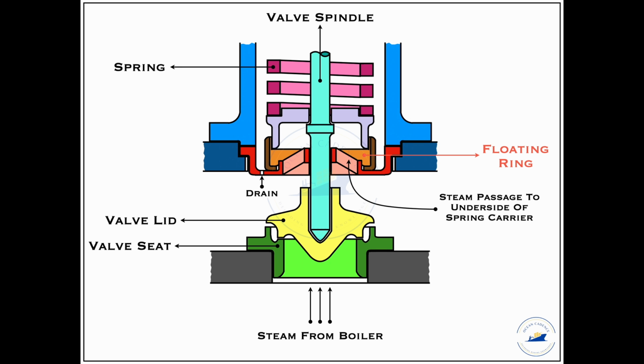It is also to be checked that there is no significant deterioration in the floating ring and there are no visible marks, scratches, or any other kind of indentations present on the surface. Upon setting, the floating ring should completely retain its place and should not have any kind of deformation.